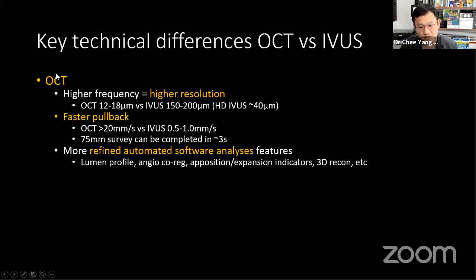And also because OCT gives us such clear pictures, the software can perform certain measurements and certain analyses automatically. That helps us to perform certain measurements. It gives us the lumen profile, which we'll see later on. There's also the co-registration function with OCT. There are these apposition and expansion indicators, which are semi-automatic with OCT as well. And OCT also provides us with a 3D reconstruction of the vessel, which can be useful sometimes.